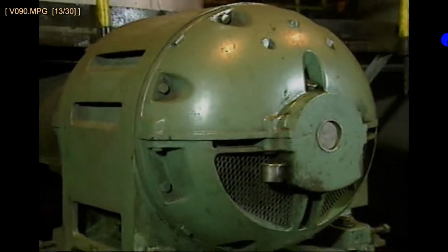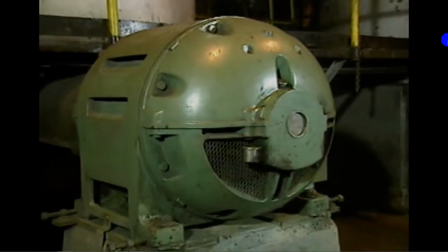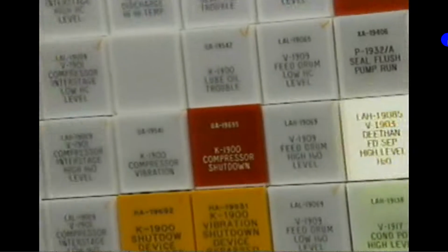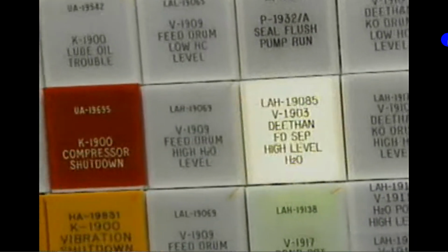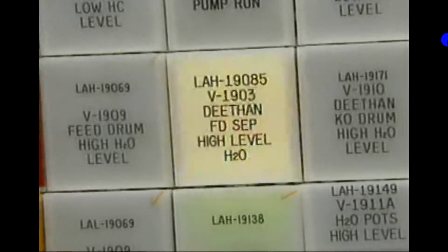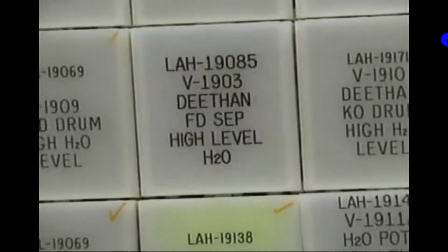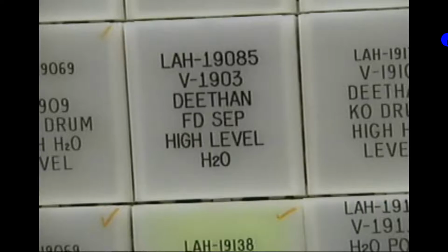For example, a pilot device can be used to sound an alarm or to protect a motor that a controller operates. A pilot device is activated by specific changes in the system in which it's placed. When it's activated, it usually either completes or breaks the circuit from the power supply through the M coil of the controller's contactor. Now, in addition to responding to changes in level, there are pilot devices called pressure switches that operate to open and close a switch in response to changes in pressure. For example, a pressure switch can be used to stop the operation of a compressor when the pressure of a gas in a storage tank has reached a desired level.